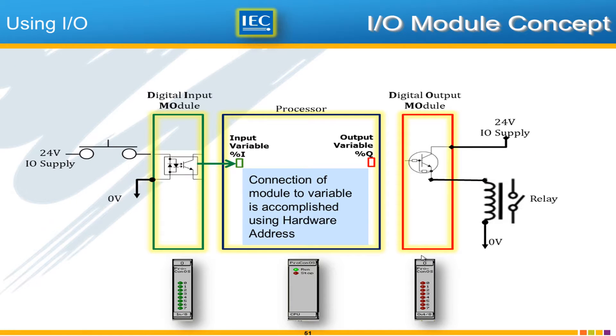That brings us to the IO module concept. On the input side, the digital input module is really just a way for a simple circuit — a simple switch — to turn on and off an optically isolated input inside the module. This is the interface into the PLC. The processor will see an input variable indicated by the syntax %I followed by a specific address, called the hardware address. Likewise, the processor controls output variables given by %Q, and those output variables control the real-world output module, which causes a flow of electric current to energize a relay that raises or lowers the gate.